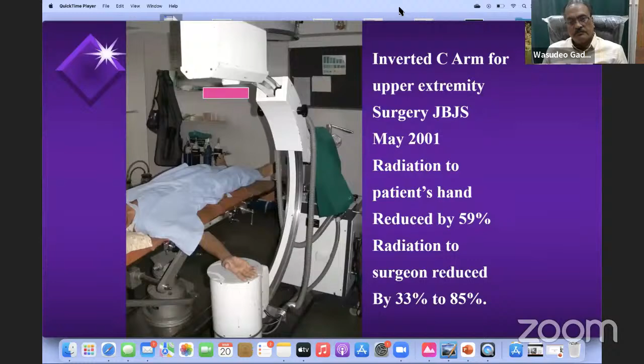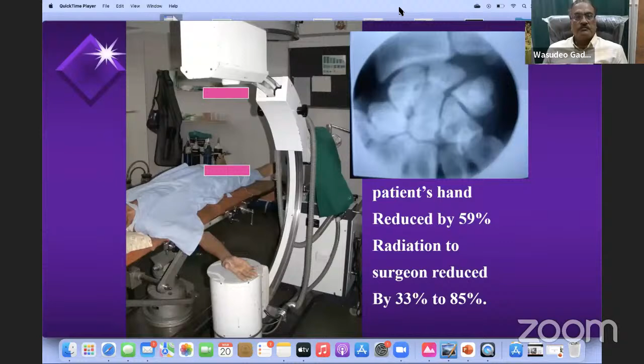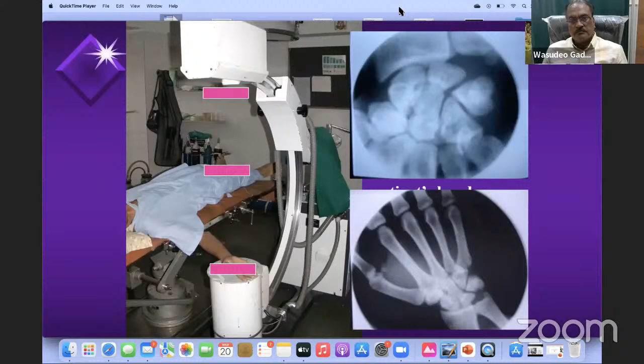The reason is, if you keep the body near the X-ray tube, only a smaller area will be seen. Whereas if you keep the hand on the image intensifier, more area can be seen. So better picturization happens, and repeated shoots are avoided. So it has reduced the radiation by almost 60% if you use the X-ray itself as a table for small moving parts.